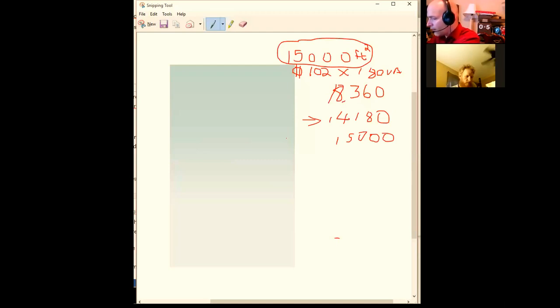equipment there. If I've got 4 receptacles on there, then I change my counting from 180 per yoke to a value that is just 90 per receptacle instead of 180 per yoke. So a single simplex receptacle would then count as 90 instead of 180 because it goes by the receptacle, not the yoke at that point. But on the wall, in any kind of building, doesn't matter what kind, as long as it's not residential, if it's in a wall, then it's 180 VA per yoke. So a simplex would be 180 VA, a duplex would be 180 VA, and a quad would be 360, 180 for each gang.